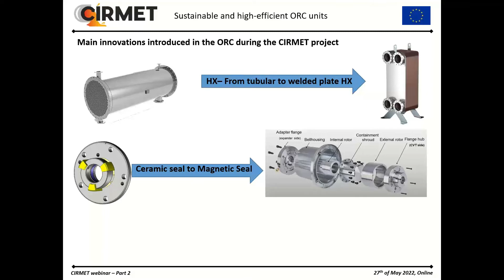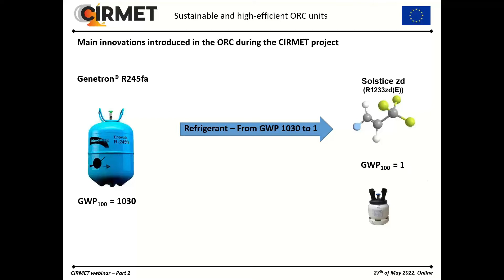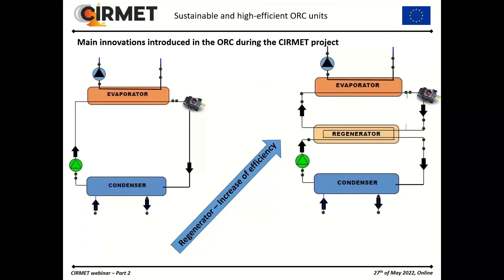Substitution of the current working fluid for a new one with very low global warming potential is required by EU regulations. Traditionally, ORC systems use R245FA as refrigerant inside the cycle. R1233ZD has a global warming potential of 1 instead of 1030 for R245FA. This innovation makes the system more compact, safer, and environmentally friendly. Finally, the introduction of a regenerator in the system to preheat the refrigerant coming from the pump with the remaining heat released in the expander increases the global efficiency of the ORC unit. The regenerator is also a welded plate heat exchanger.